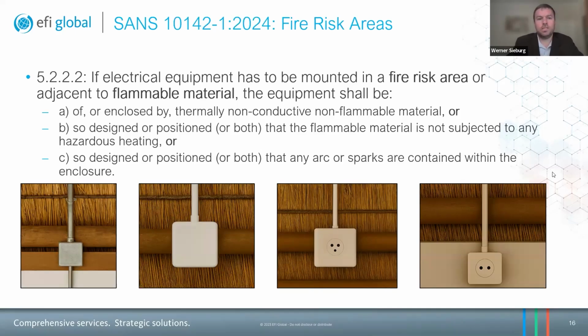Because then, clauses B and C basically state that it shall be so designed or positioned or both. So I think the middle two pictures are basically if you can ensure that it is a non-thermally conductive, non-flammable material, the mounting position could potentially be near the thatch, right? Because the preposition between A and B and C is definitely an or, and I've actually highlighted that in bold. Because if you adequately ensure that it is non-flammable, non-conductive, you don't need to pay attention to number B and C. But I think one must also be rational and be cognizant of the heating effects.